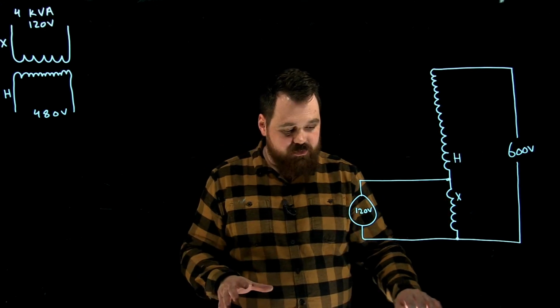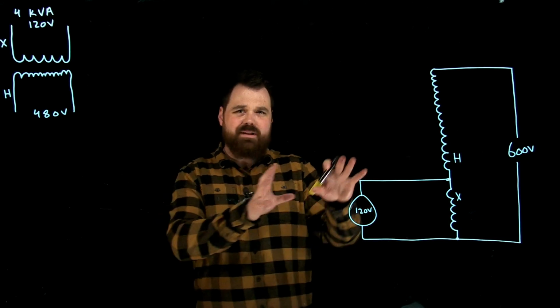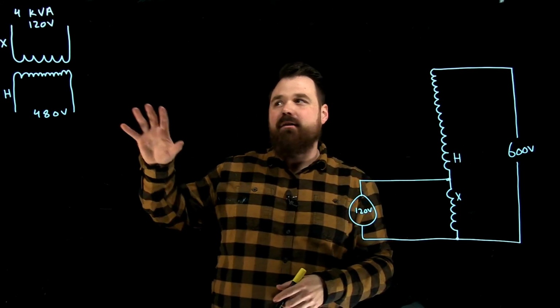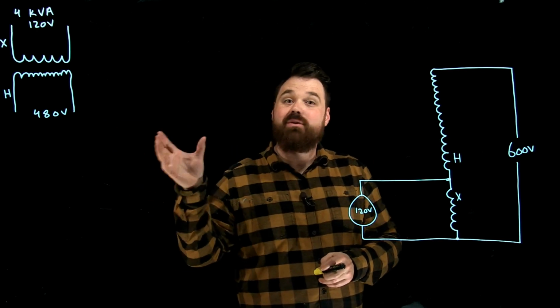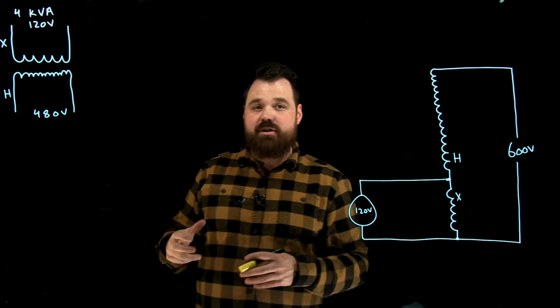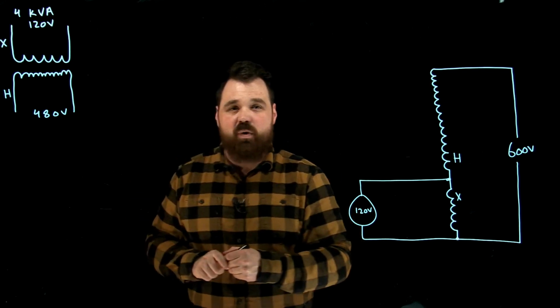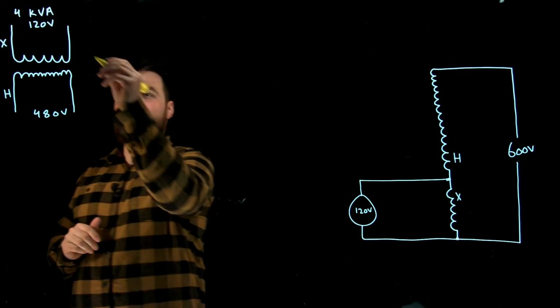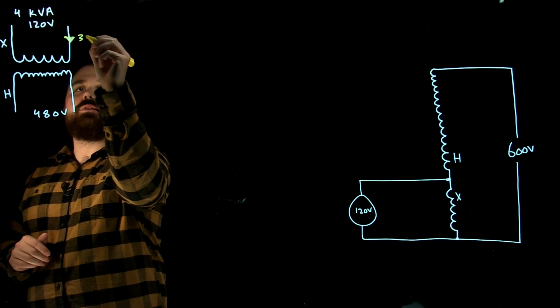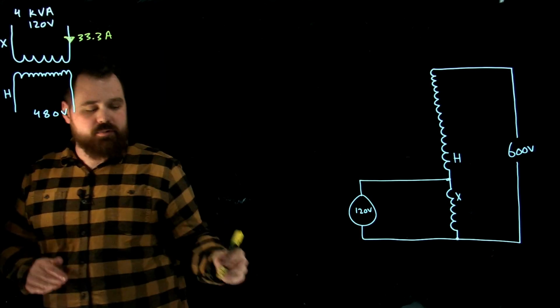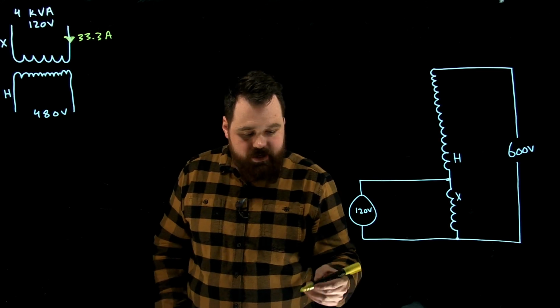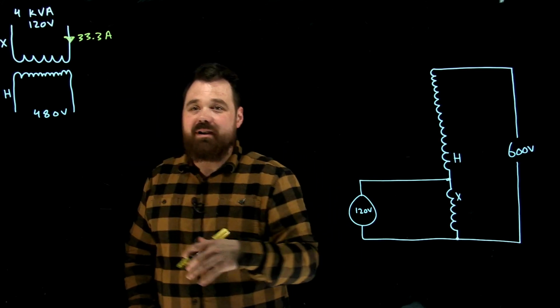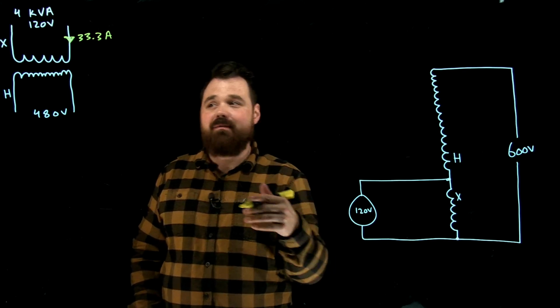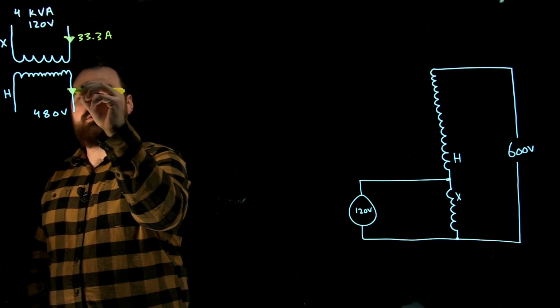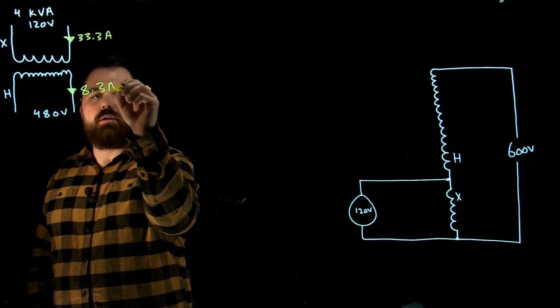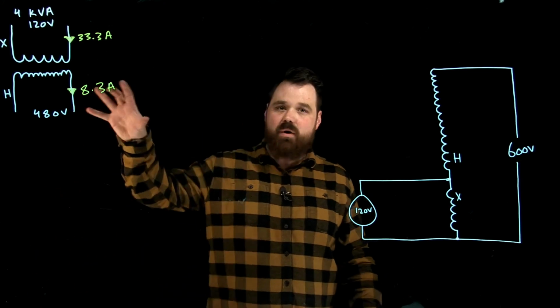Now, before we get too much more into it, I always like to start, before we do the math, by figuring out our numbers as the mutual induction transformer. So if this mutual induction transformer is 4 kVA on the X winding, the 120 volt winding, that rated current would be 33.3 amps. Okay, so if the rating is 33.3 amps on the X winding, my H winding, 4,000 VA divided by 480 volts, my rated current down here would actually be 8.3 amps. So that would be my rated current on both of those.